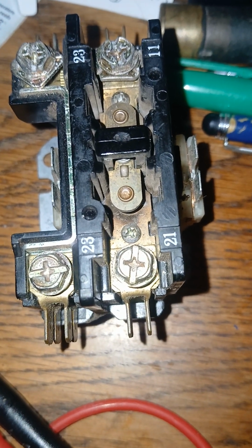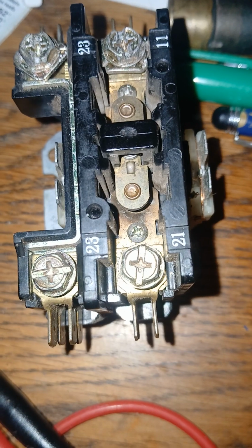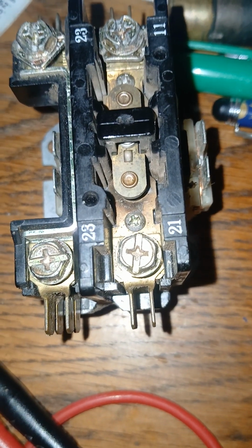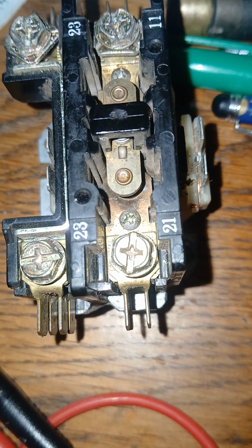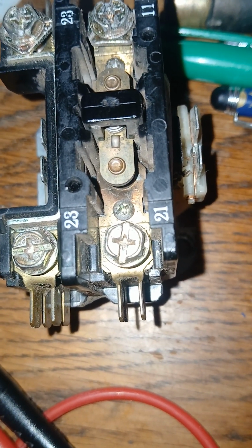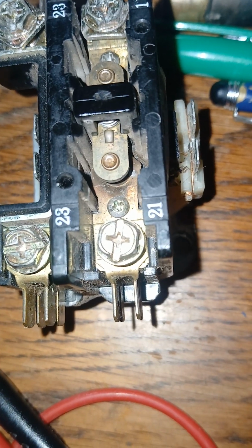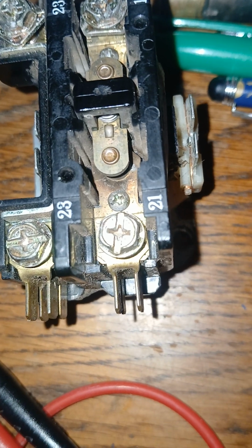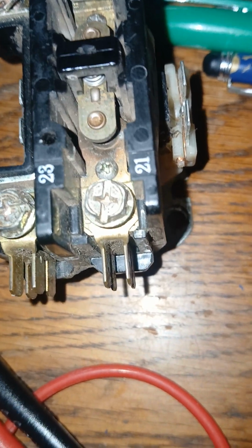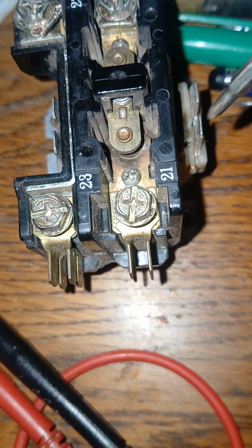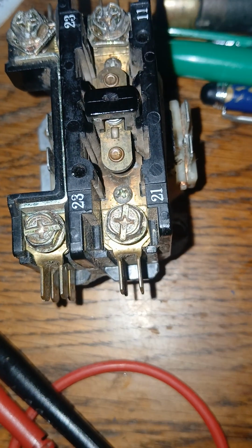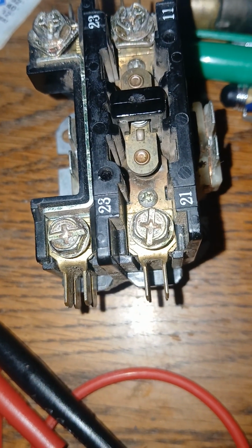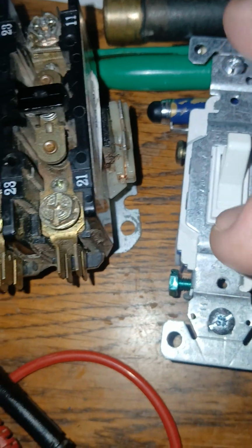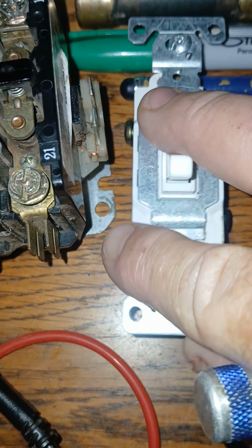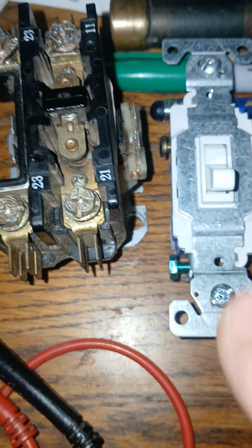Now, the beautiful thing about this contactor, for instance, if you're running a fan motor or a compressor, you don't want to run it incessantly. What that means in layman's terms is you need to give it a break when it hits the satisfactory point on the thermostat. Say, for instance, you were at 70 degrees, it hits 70 degrees. Okay, the thermostat no longer sends this low voltage over here, so you're not getting voltage over here. It will actually cut the electricity off, similar to a light switch, but where you manually flip a light switch, this is controlled electronically. Then you de-energize the coil and you cut it off.